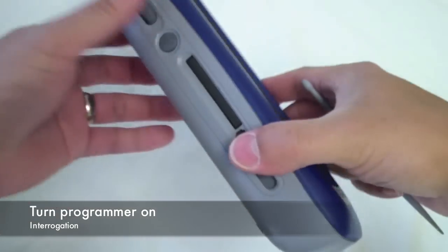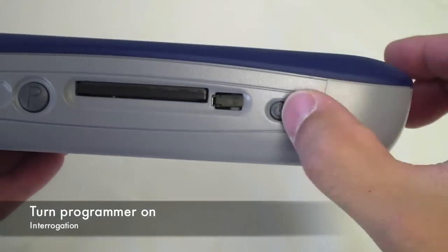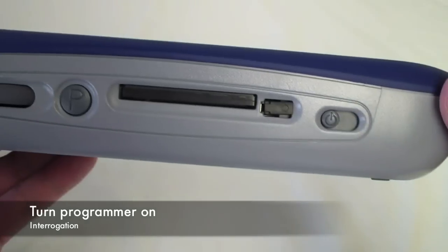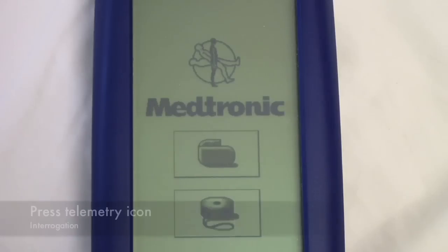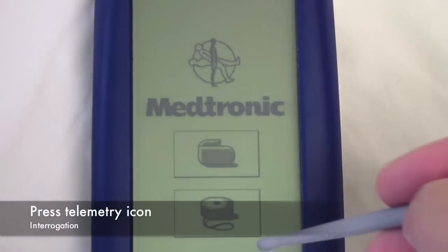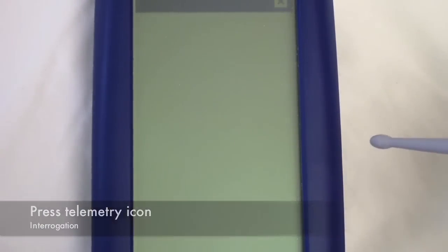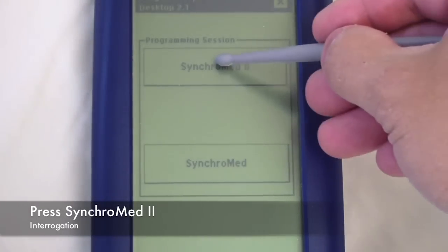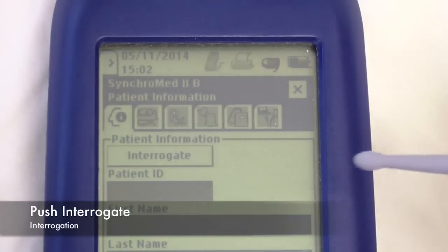Turn the programmer on by sliding the power button on the left side. Press the telemetry icon, which is the second button. Then press Synchromed 2. Press the interrogate button.